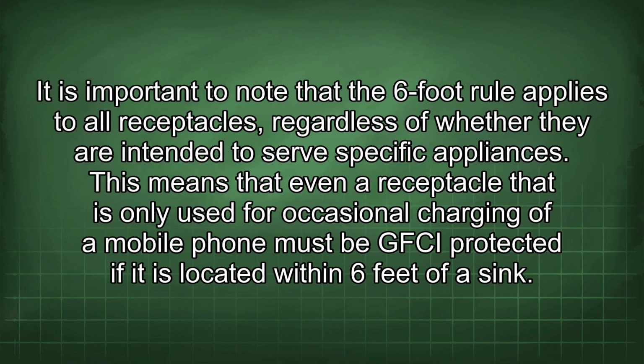It is important to note that the 6-foot rule applies to all receptacles, regardless of whether they are intended to serve specific appliances. This means that even a receptacle that is only used for occasional charging of a mobile phone must be GFCI protected if it is located within 6 feet of a sink.